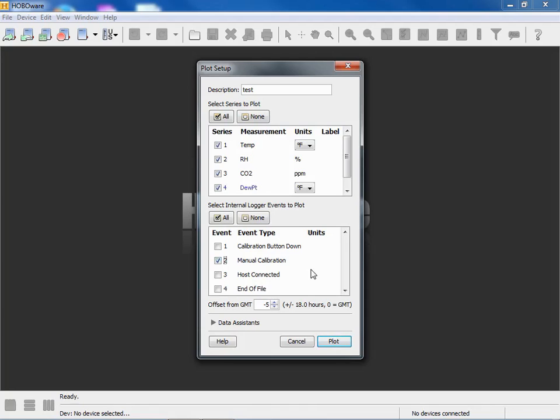Again, we have the ability to put in an offset from GMT, or what is called UTC time, just like any other logger from Onset. The logger gets its date and time from the device that it's being launched from, be it a computer, a smartphone running the Hobo mobile app, or a tablet or a shuttle device.